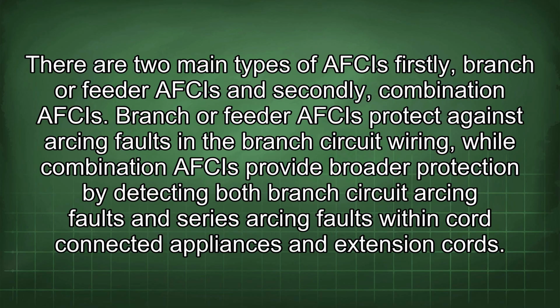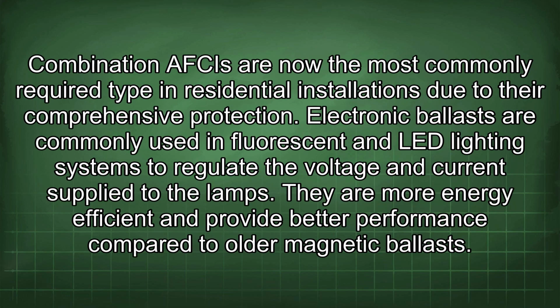There are two main types of AFCIs. Firstly, branch or feeder AFCIs, and secondly, combination AFCIs. Branch or feeder AFCIs protect against arcing faults in the branch circuit wiring, while combination AFCIs provide broader protection by detecting both branch circuit arcing faults and series arcing faults within cord-connected appliances and extension cords. Combination AFCIs are now the most commonly required type in residential installations due to their comprehensive protection.